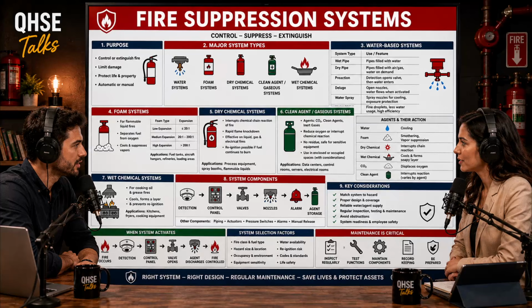That's brilliant. So one is for invisible particles, one is for visible. Right. Photoelectric detectors are much better at detecting slow, smoldering fires like a cigarette in a couch cushion, because those fires produce larger, highly visible smoke particles. Okay, so if smoke detectors are so good, why do we use heat detectors at all? Because smoke detectors are prone to false alarms in specific environments. If you put an ionization or photoelectric detector in a commercial kitchen or a dusty woodworking shop, they will go off constantly, because the dust or steam mimics smoke. Exactly. In those environments, you have to use heat detectors. They're slower to react, but they are highly reliable and much less prone to false alarms.